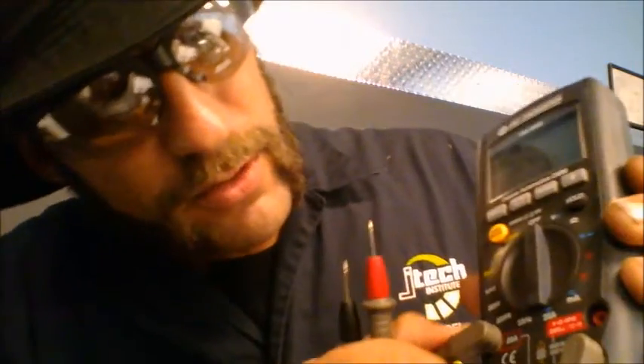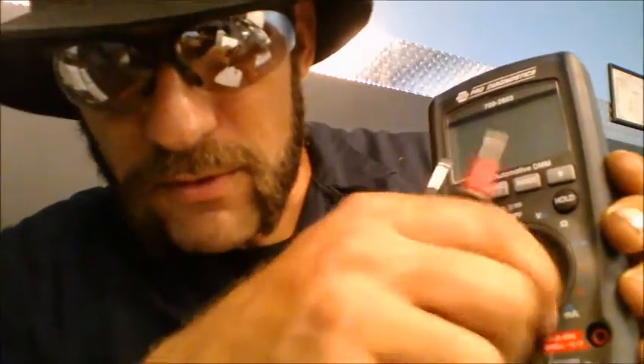Now, when setting your multimeter up for amperage checks, you need to put the multimeter in as part of the circuit. In order to protect the multimeter, you're going to use the fused links. On this one, they're on the opposite side. You have a 20 amp and a milliamp. You should always go with the greatest protection, not knowing what you have there. And then you would set it, so we're going to do ours in the 20 amp, and you would set it for the 20 amp. And then you would place it in series in the circuit. If it only reads in milliamps, then you can go ahead and go down to the milliamp port.